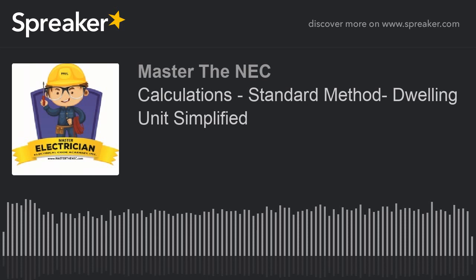Okay? All right. So we're now in the dwelling unit, and it's 3 VA per square foot. And, of course, the general use receptacles are all incorporated in here. So the first thing we want to do is try to determine our general lighting and receptacle loads based on 220.12 in the associated table. And so we know that it's 3 VA per square foot. So we'll do 3 times, and what was our square footage? It was 2,500. So it's 3 times 2,500 equals 7,500 VA. So you would write that down. That's number one. That's the first value that you're going to write down.